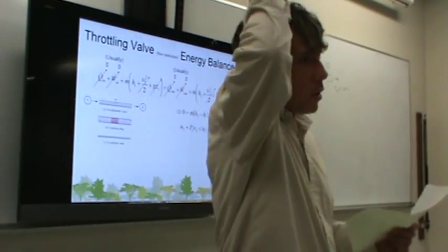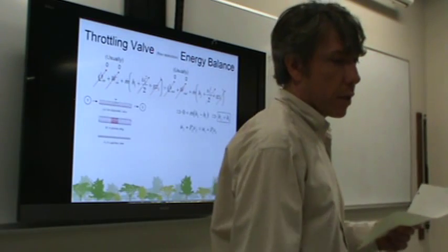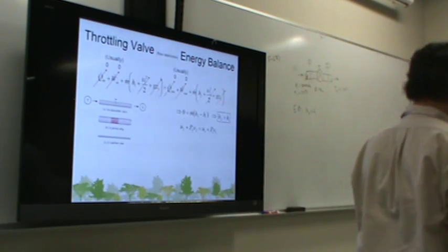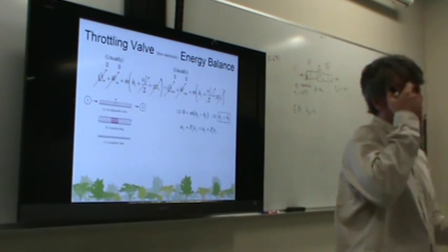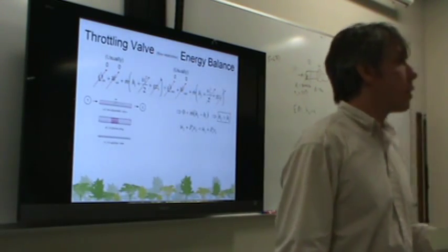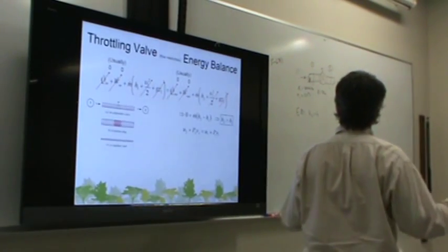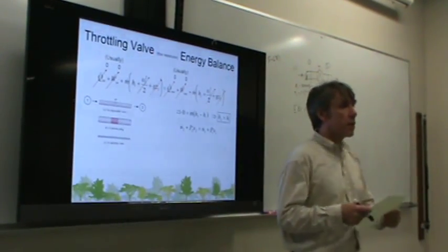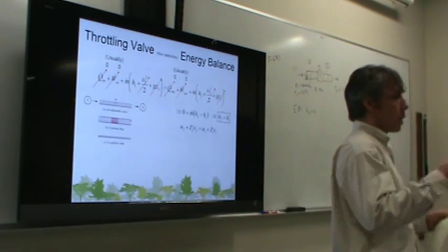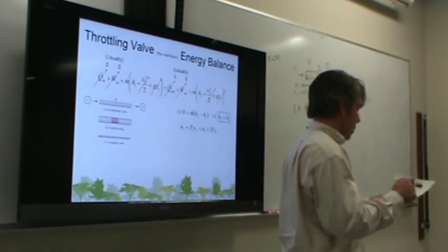Saturated R134A? Yeah, saturated R134A. There's no 25 degrees Celsius, there's 24 and 26. But what's the pressure at those two? 646 and 685. They're both lower than what we have, right? So what does that tell you about the state of the incoming refrigerant? It's subcooled, that's right. It's definitely liquid, it's subcooled.